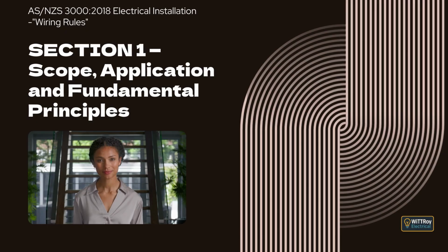Clause 1.6.1 General. An electrical installation must be designed to keep people, animals, and property safe. It must work properly for its intended use. It must connect and operate safely with the electricity supply it is attached to, and it must not create problems for the distribution system. It must allow safe operation, safe inspection, safe testing, and safe maintenance. And it must reduce inconvenience if a fault happens.